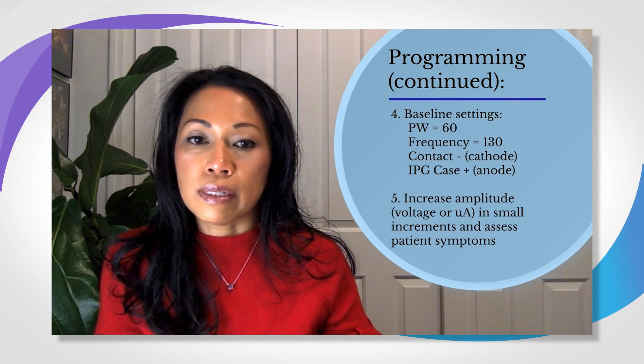The baseline settings most centers use are a pulse width of 60 and frequency of 130. As I said earlier, the negative contact is the active one, so we set the bottom contact as the negative or cathode, and the battery as the anode or positive. Then we increase stimulation slowly, in voltage or milliamps, in small increments, assessing patient symptoms as we go—looking for benefit or side effects.